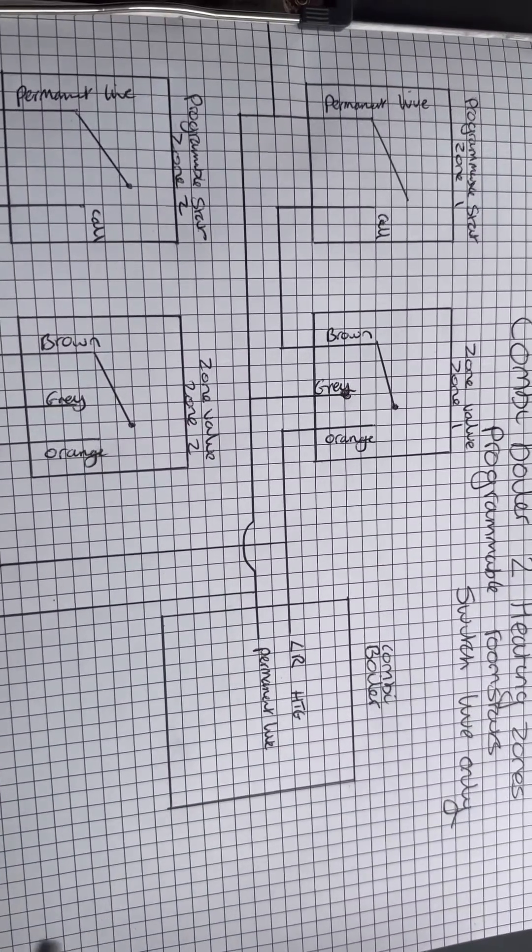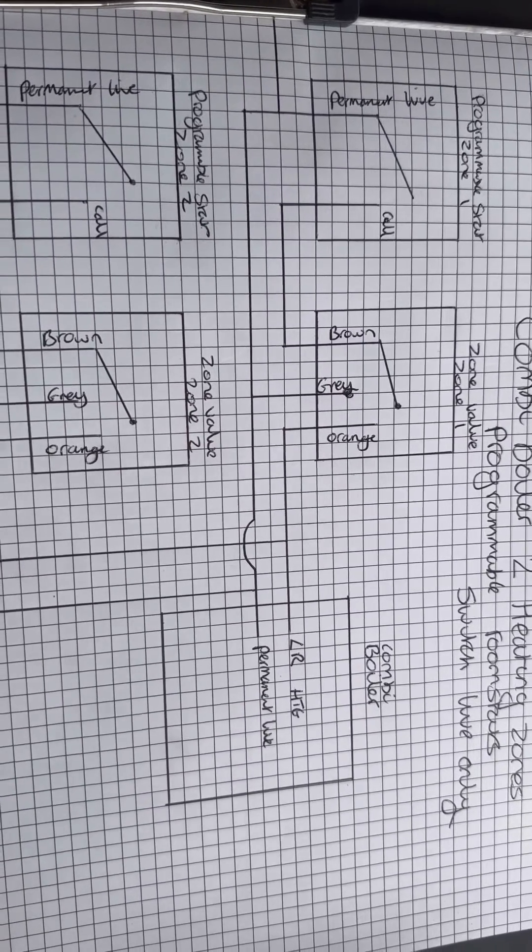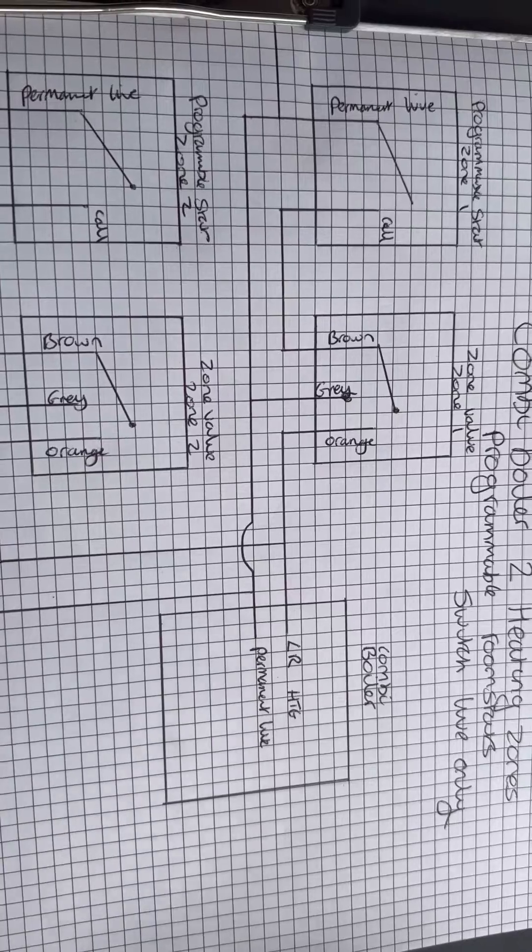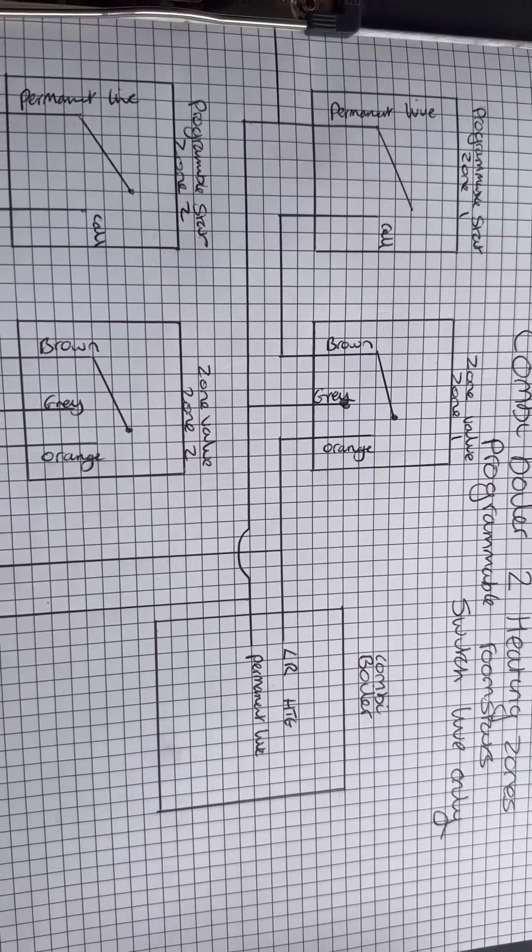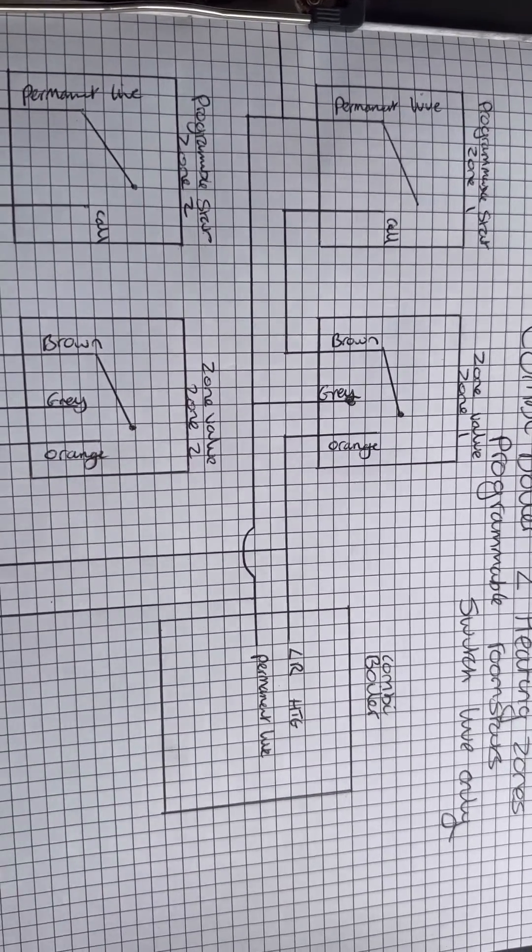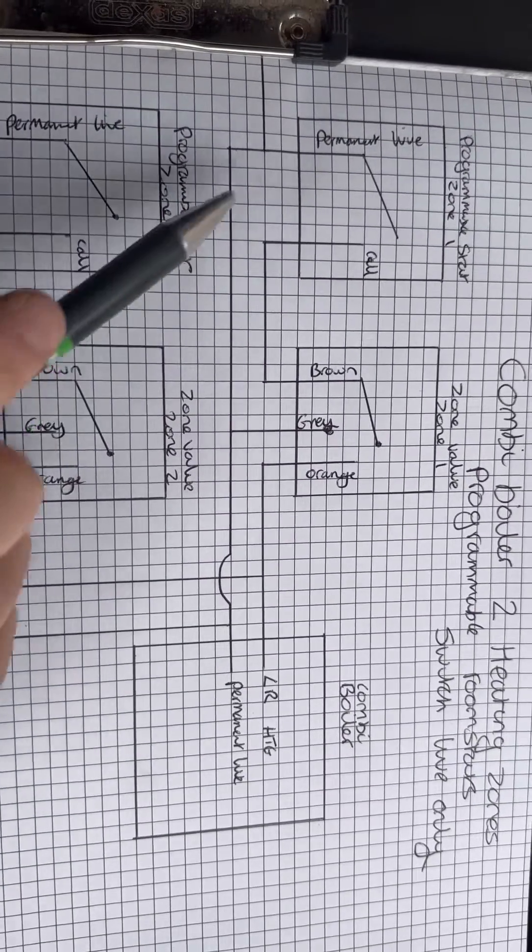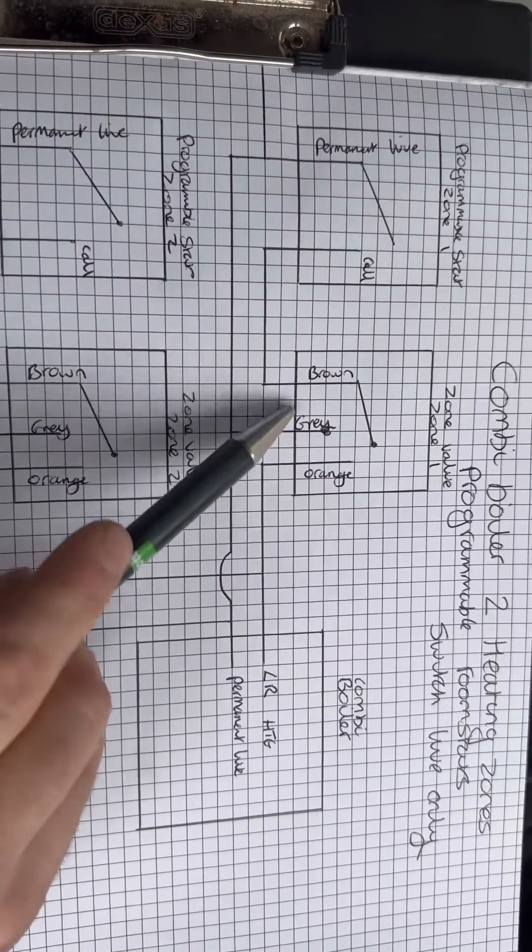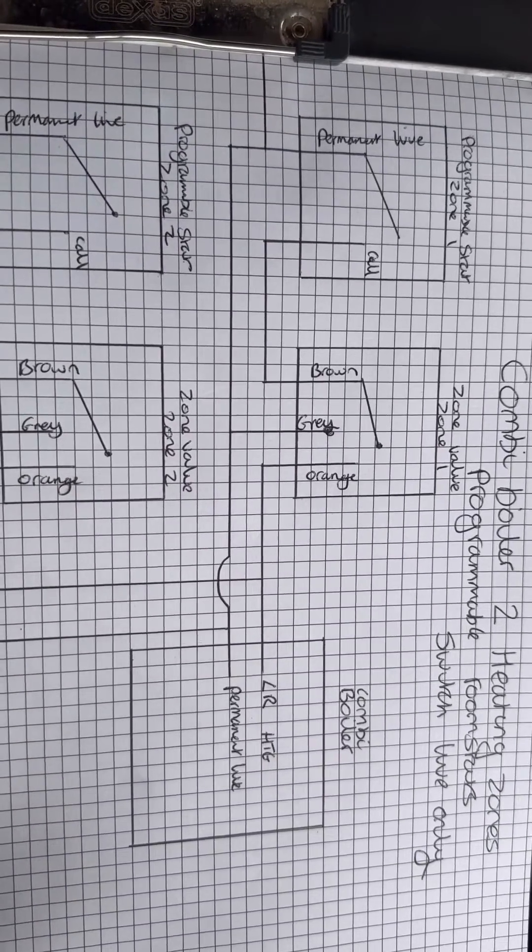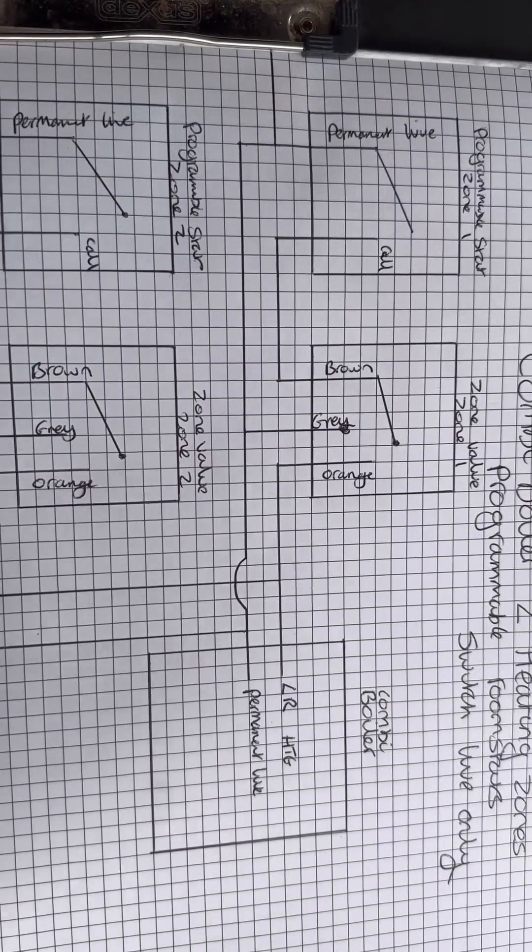So I thought I'd draw this diagram so that you can see a combi boiler with a programmable stat for the zone downstairs and upstairs. So that's two programmable stats, two zone valves. You can call it an S-plan but combi with two zone valves. So we've got permanent live to both programmable stats and the boiler has a permanent live also. And then you've got permanent live to grays on the two zone valves. So on this one, for example, the heating was on constantly downstairs.